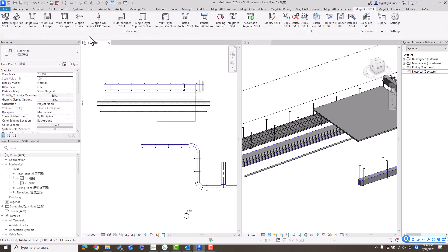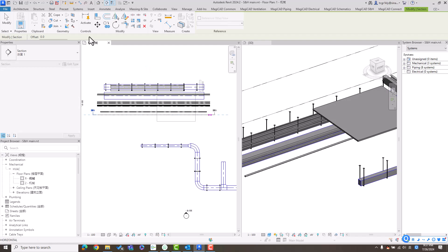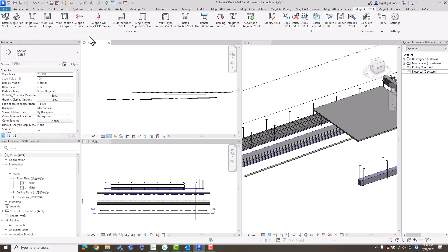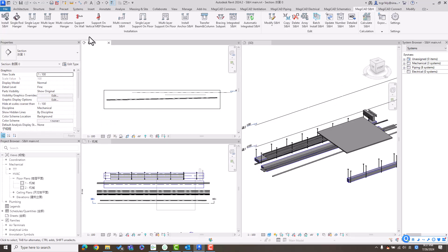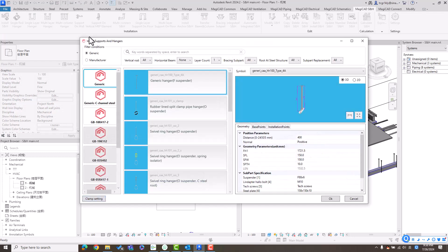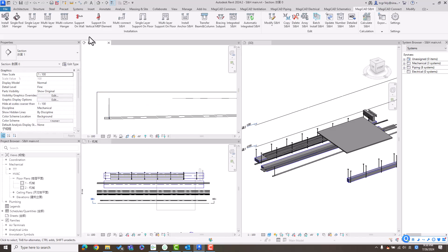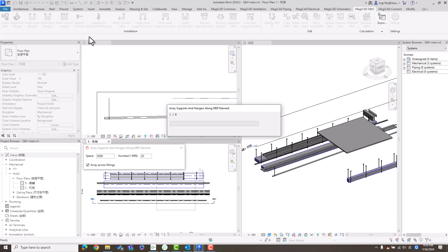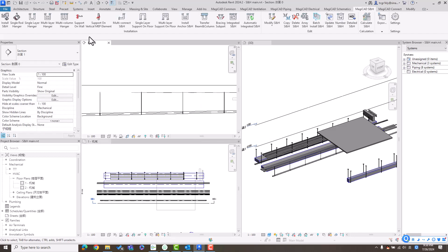Here is a pipe with slope. I can make a section view like this. No matter in the plan view or in the section view, I can install a simple support hanger — like a single rod hanger — select the pipe, select a suitable type, and click OK. Then I install the support hanger instance. Using the array function, I make some copies: select the instance, select the direction, wait a few seconds, and get the result. You can check the result in the section view — it also attaches to the slab automatically. If there is no slab, it connects to the top level automatically.